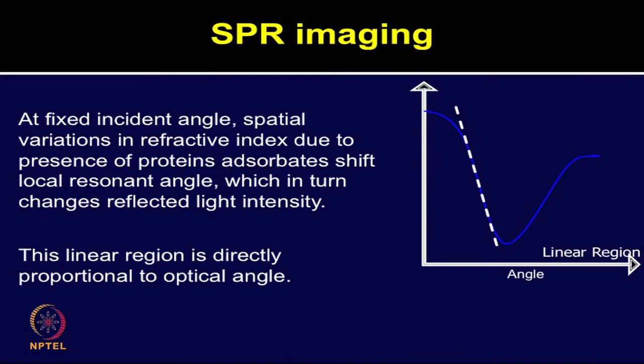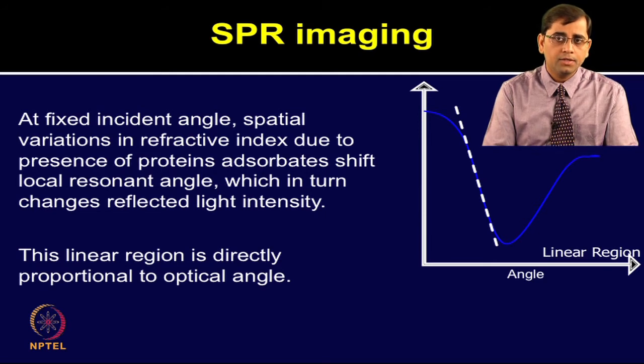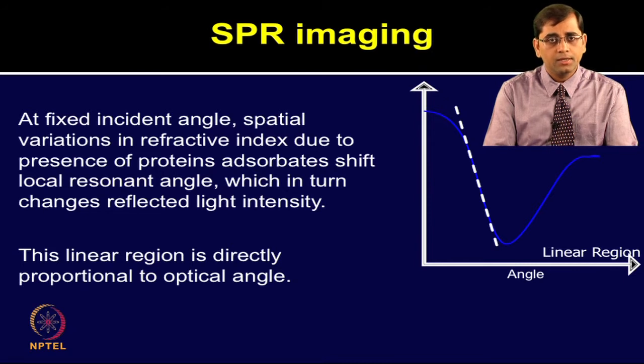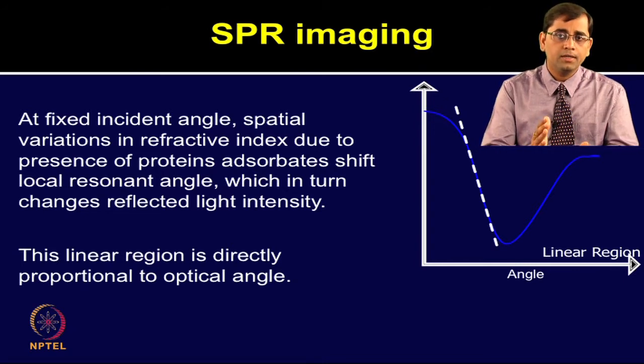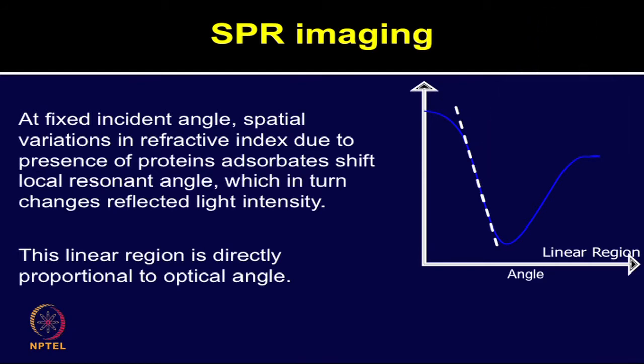At a fixed incident angle, the spatial variations in refractive index due to the presence of protein or other molecule adsorbates shifts the local resonant angle, which in turn changes the reflected light intensity. This linear region, as shown in the graph, is directly proportional to the optical angle. This linear region of the SPRi curve quantitatively correlates the changes in reflected light intensity with the amount of material present on the surface.